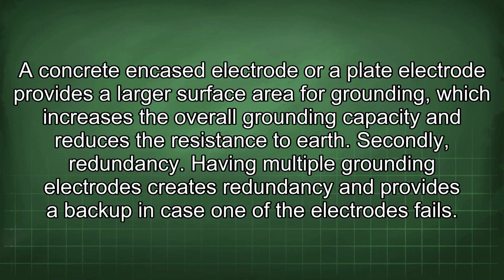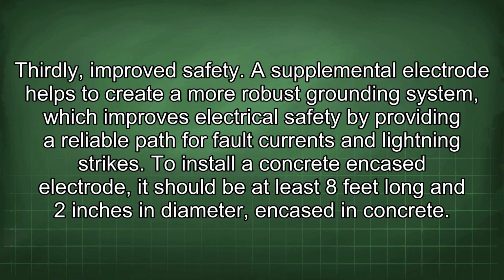Secondly, redundancy. Having multiple grounding electrodes creates redundancy and provides a backup in case one of the electrodes fails. Thirdly, improved safety. A supplemental electrode helps to create a more robust grounding system, which improves electrical safety by providing a reliable path for fault currents and lightning strikes.